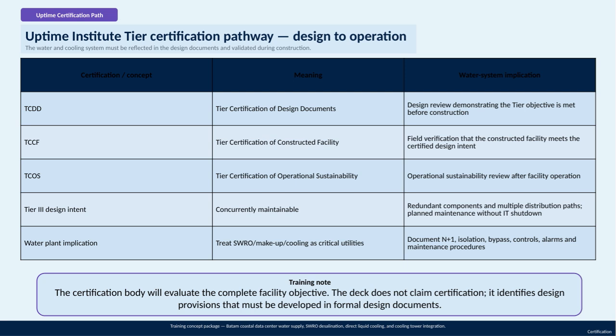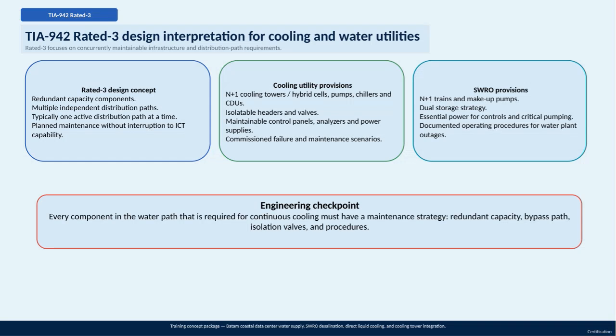to move towards certification. This slide focuses on the TIA 942 rated 3 design interpretation, specifically related to cooling and water utilities in data centers. Rated 3 emphasizes concurrently maintainable infrastructure, meaning all critical components must support maintenance activities without affecting overall ICT operations. The key concept here is redundancy and multiple independent distribution paths. Although typically only one distribution path is active at a time, others are fully capable of taking over if maintenance or failure occurs. This allows planned maintenance without any interruption to the data center's operations.